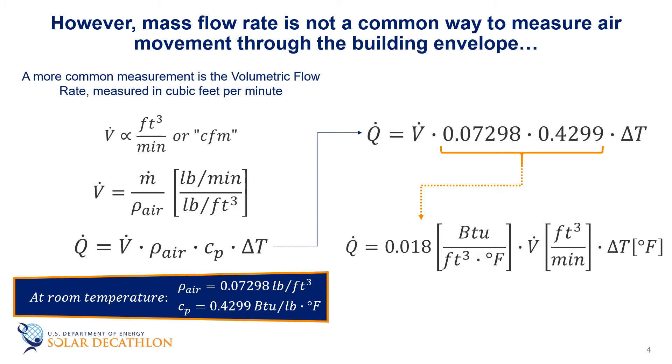This ΔT is the temperature difference required to heat the outside air to the comfortable inside temperature. Notice that the 0.018 has units, which are BTUs per cubic foot degree Fahrenheit. If you're working in the metric system, you'll end up with a different constant in a different set of units.